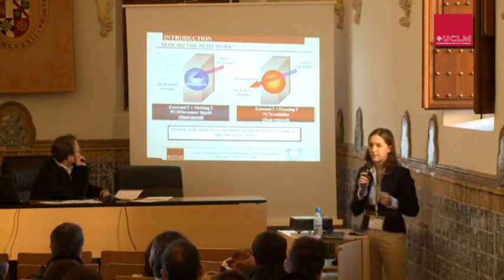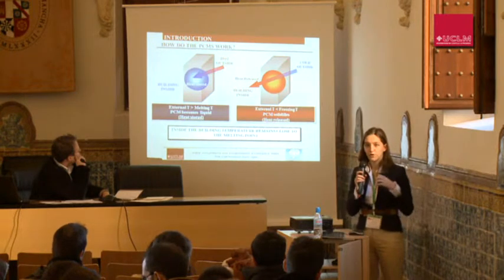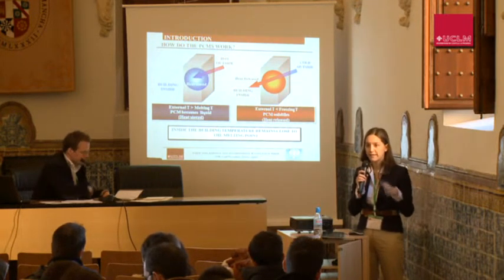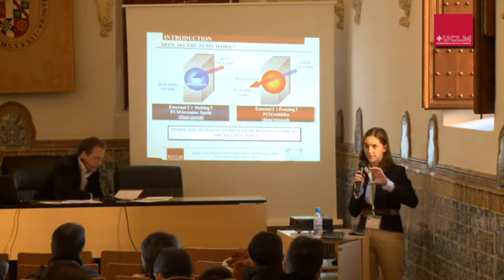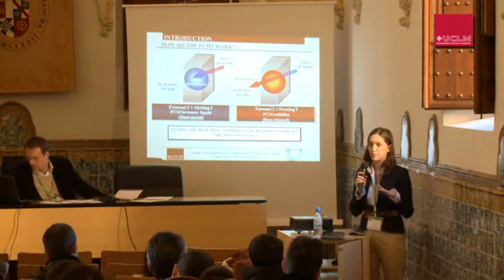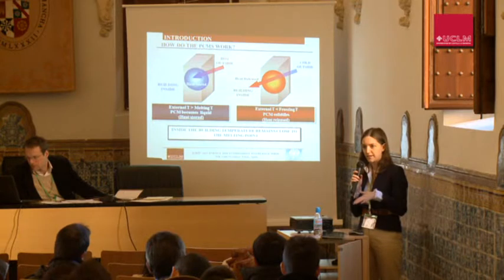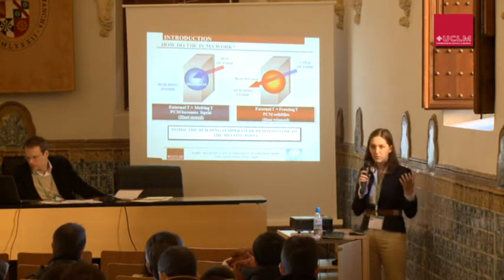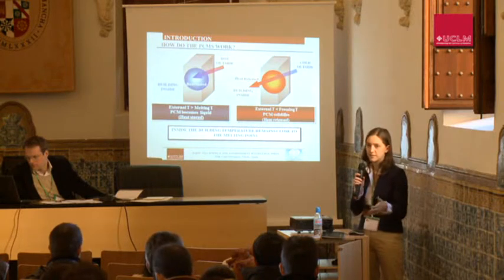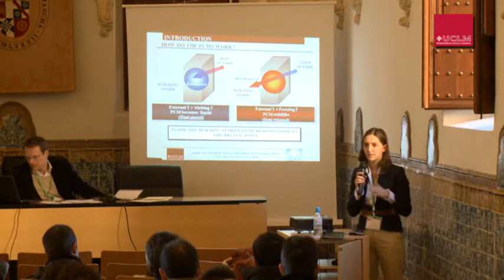How do they work? When the temperature outside is higher than the melting point of the PCM, the PCM starts to melt, so all the energy is spent in the phase change, meaning the temperature stays constant at that value. For example, if you choose a PCM of 25°C, during the melting transition you will have this temperature inside the building. On the contrary, when it's cold outside — for example, during the night — the PCM releases this heat, again keeping the temperature constant at the melting point.